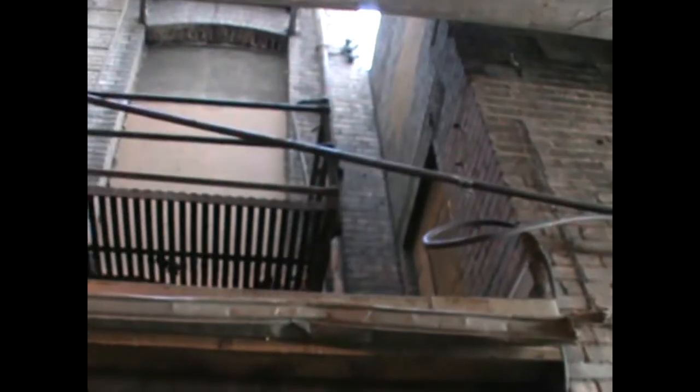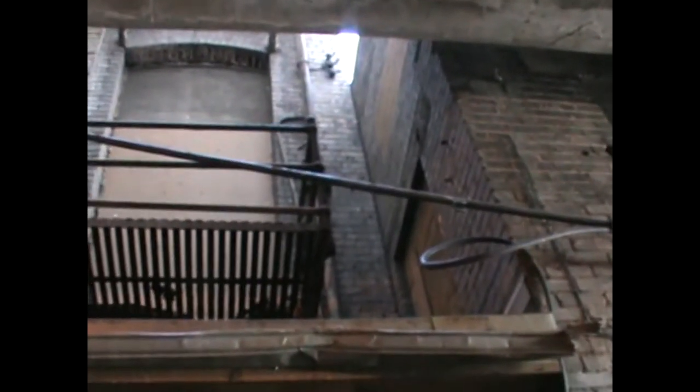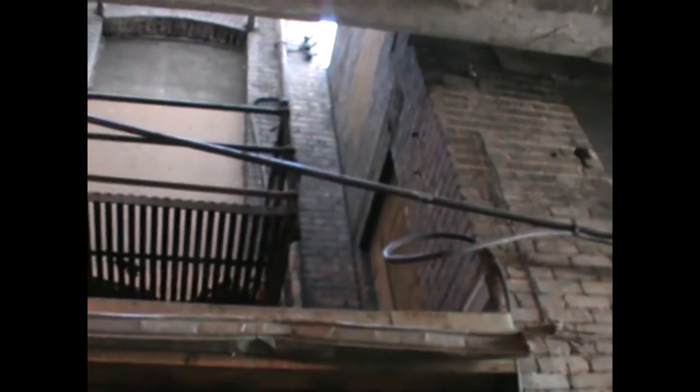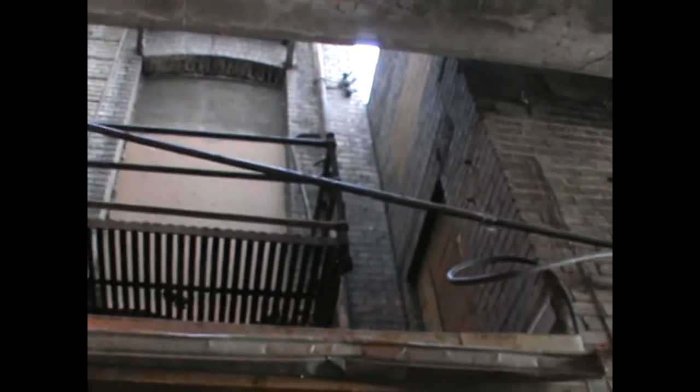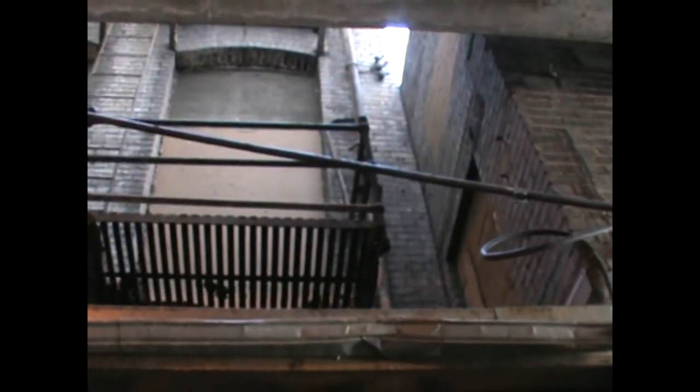So where's the standpipe? You have a standpipe there? Yeah. So now it's a life safety issue. It's an OSHA issue for your firemen. I know you guys are not covered by OSHA, correct? Right. But to get to that standpipe, and that standpipe has not been inspected, right? So now they've also blocked this access down into the basement, right?